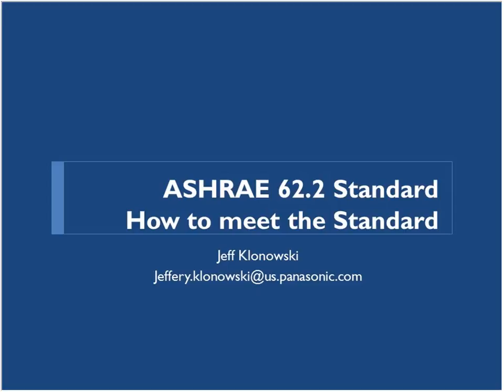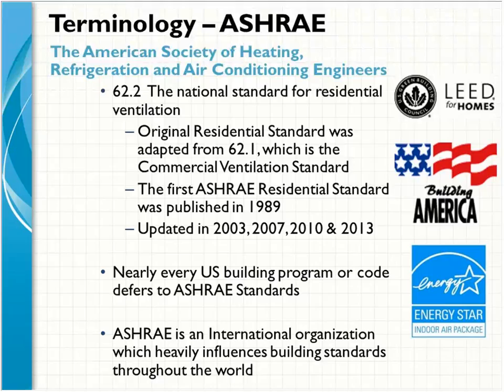All right. So now, knowing that we need to ventilate mechanically, let's move on to talking and learning a little bit about meeting ASHRAE 62.2. And I should also say that, when you're talking about building codes, oftentimes the codes themselves will not refer to ASHRAE 62.2. They'll refer to the mechanical code or the residential code, but they're referring to, or they'll use the calculations exactly as they are in ASHRAE 62.2, whether the 2010 or the 2013 version, but it won't refer to ASHRAE oftentimes in the code itself.